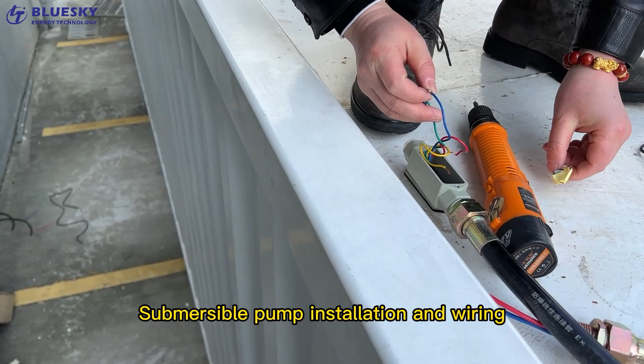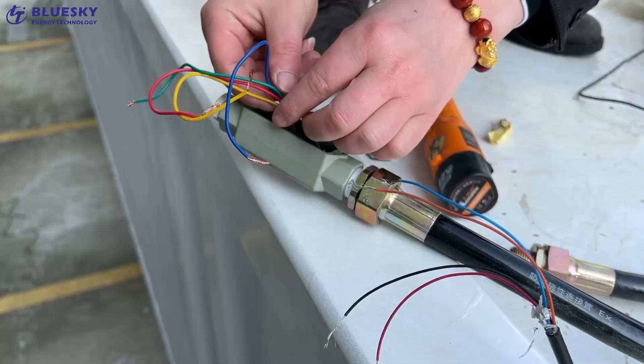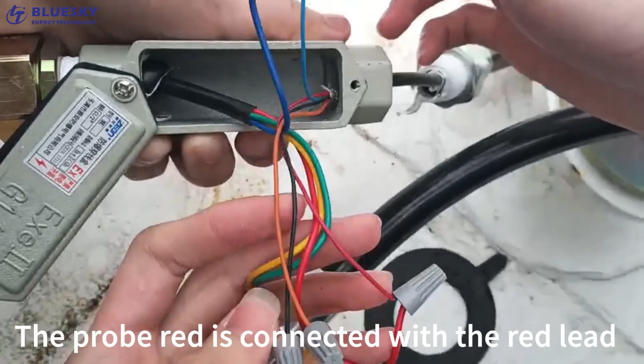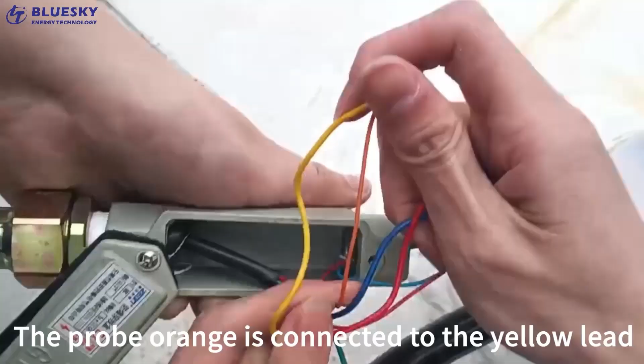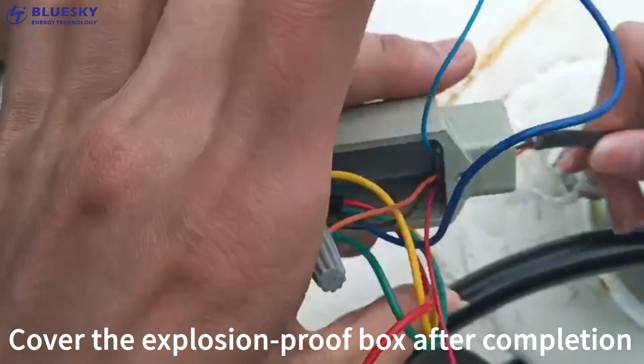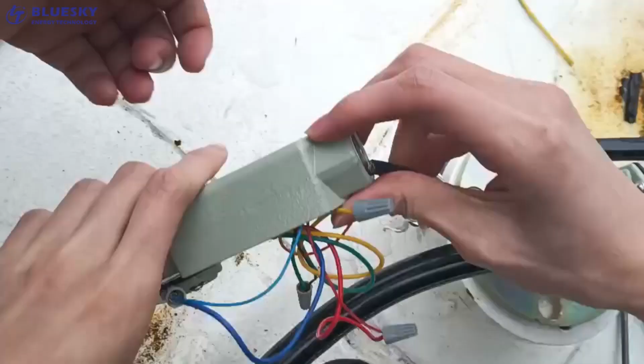Submersible pump installation and wiring. Connect the probe into the explosion-proof box. The probe blue is connected to the blue lead. The probe red is connected with the red lead. The probe orange is connected to the yellow lead. The black probe is connected with the green lead. Cover the explosion-proof box after completion.